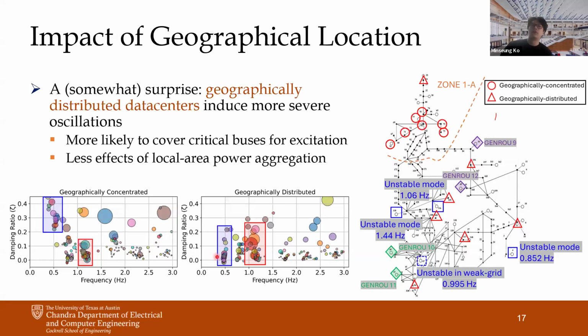Another reason why the geographically distributed cases result in a larger magnitude of oscillation is that when the data center loads are concentrated, there could be an aggregated impact from the power demand of those data centers. So there could be some cancellation of high frequency terms in the concentrated cases. That would be another reason why the distributed data centers result in a larger magnitude of oscillation.